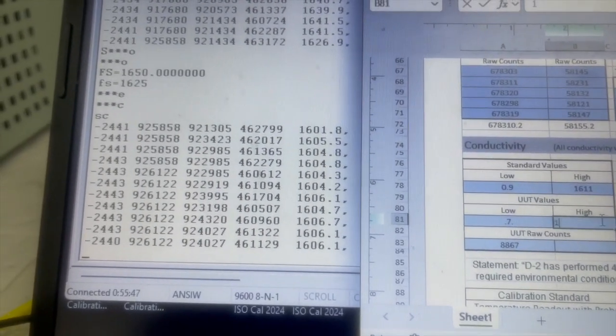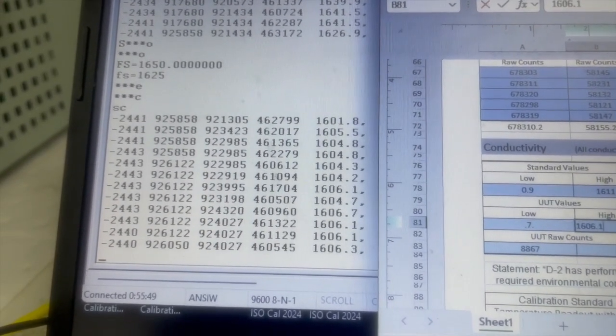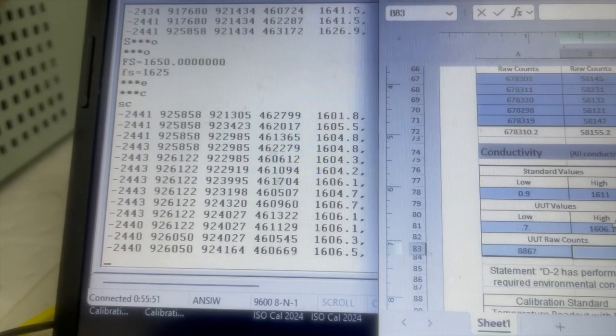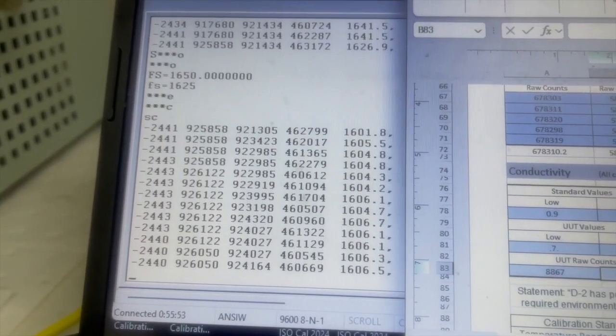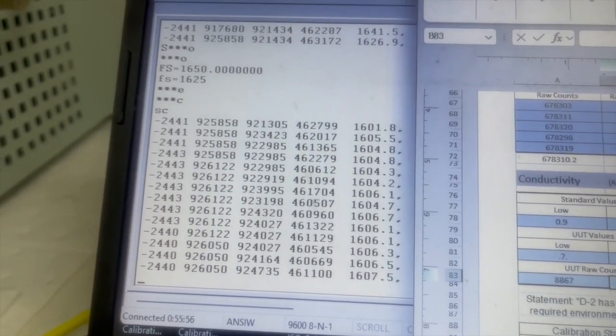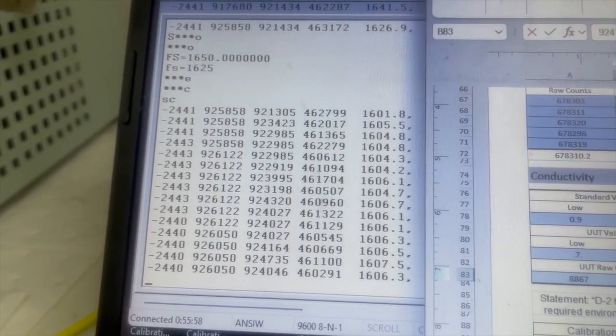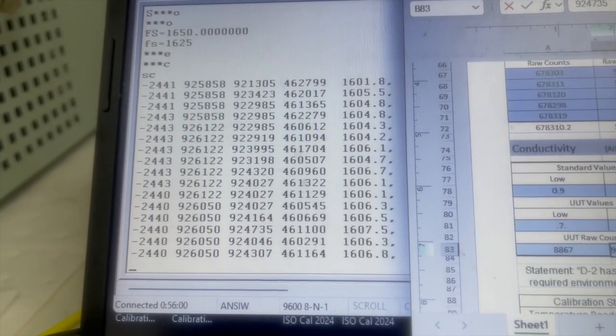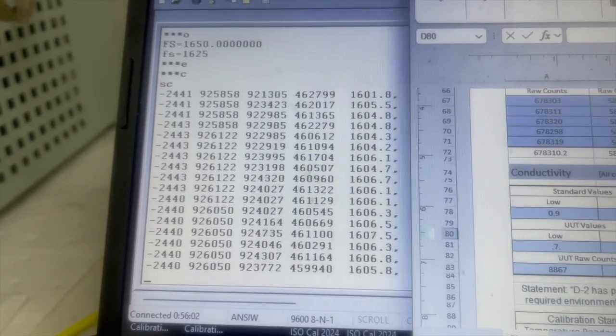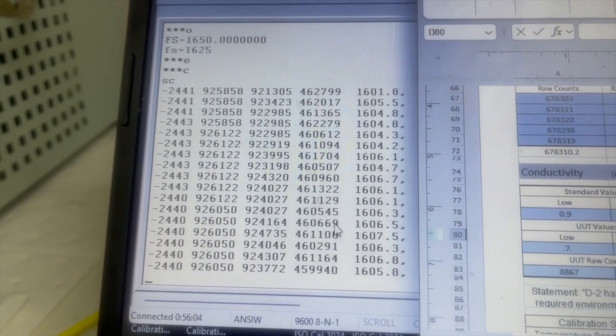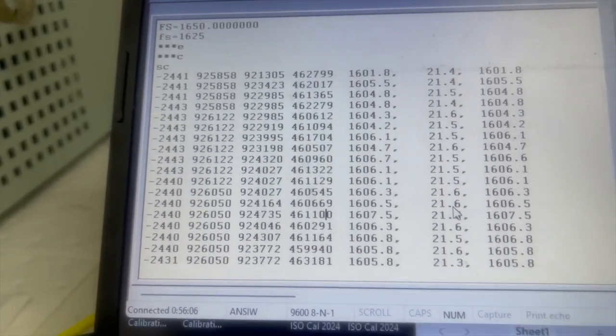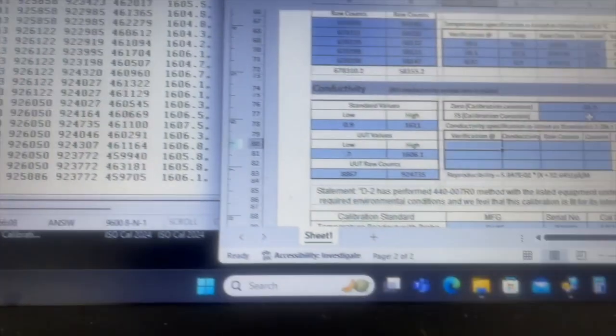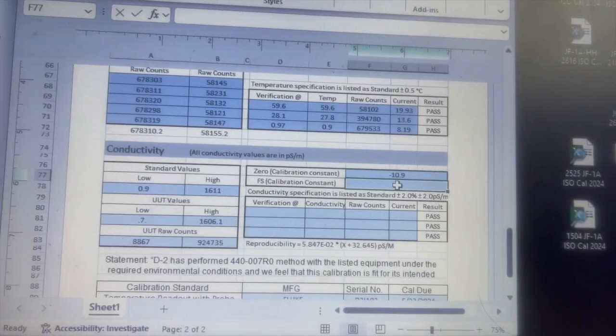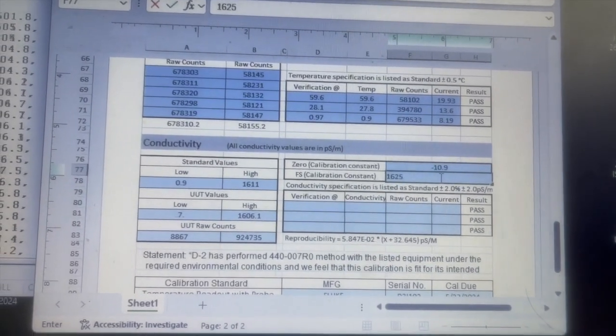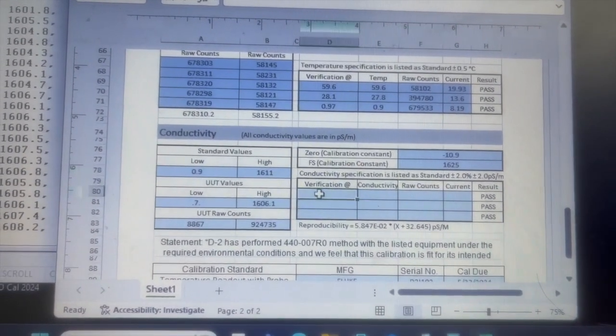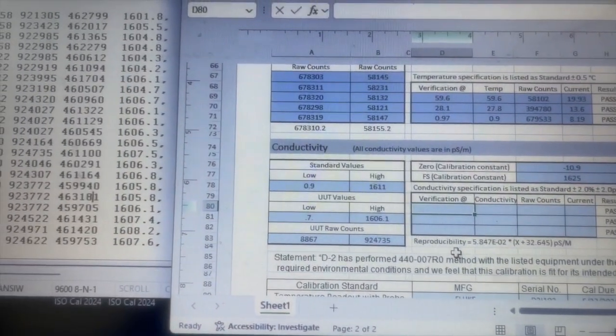So 1606.1. And our counts are 924735. Which is pretty close to a million. When you're at full scale, it should be over a million. And I'm going to record our counts, which was 1625 for that, for the full scale constant.